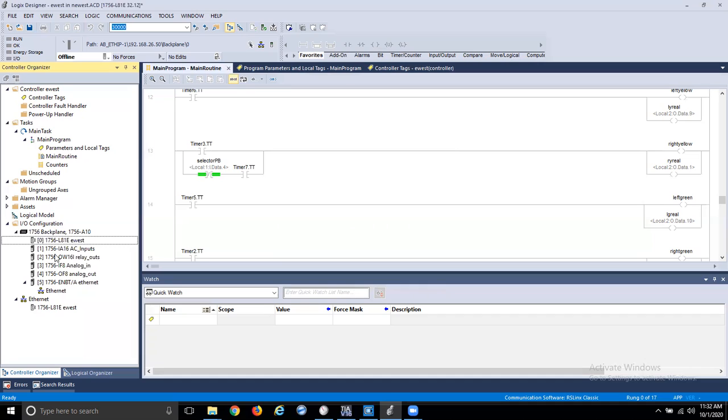One thing I've noticed about discovering modules is you need to look very carefully when you're online to see if you see a little yellow triangle that is warning you that there's some kind of mismatch. So you'll see the card, you'll see it in the tag list, you'll be able to alias to it, but if you see a little yellow warning triangle, then it probably will not work correctly, if at all. So that's one of the little things you've got to look for.